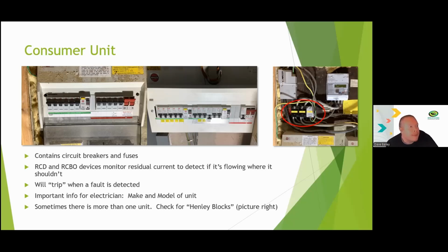Particularly for solar, because electricity flows the other way, you really want to avoid putting solar into an existing consumer unit. Consumer units are generally rated at 100 amps, and the main fuse is also 100 amps, so that's fine. However, if everything is on - kettle, lights, washing machine, tumble dryer - you might be approaching 100 amps pulled from the grid. If you're also generating solar and exporting it back, that's another 16 amps of current, so potentially you could be overloading the consumer unit with 116 amps. It's rare and unlikely, but it's good practice to keep this in a separate consumer unit.